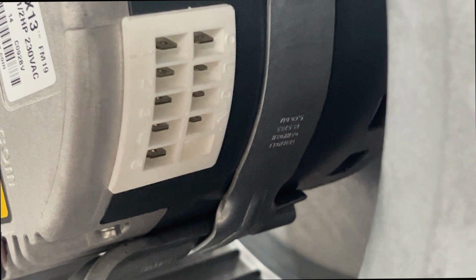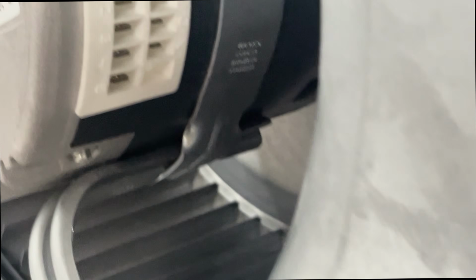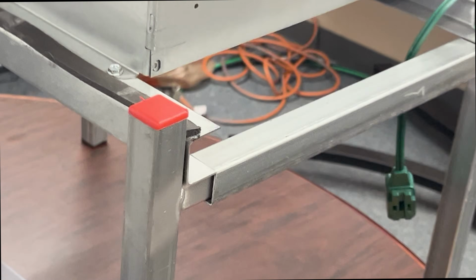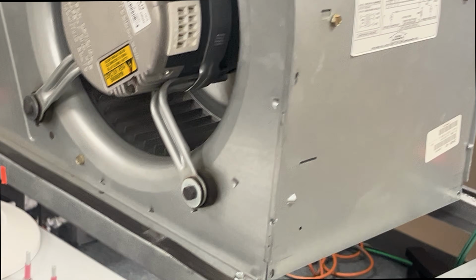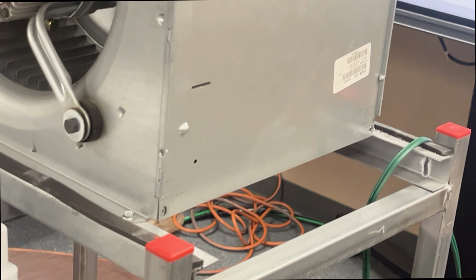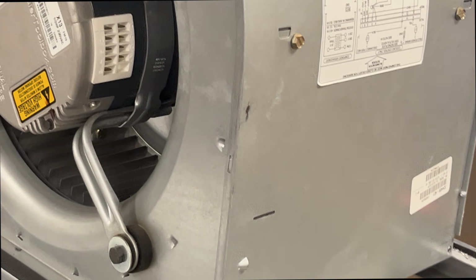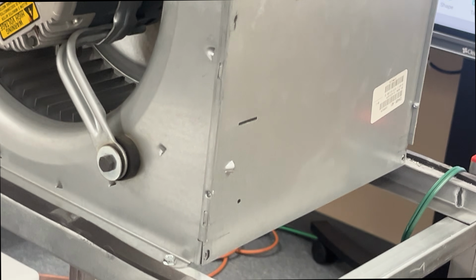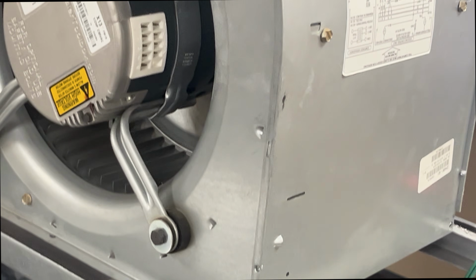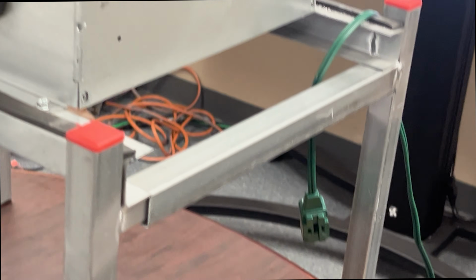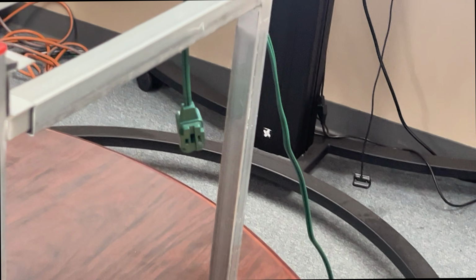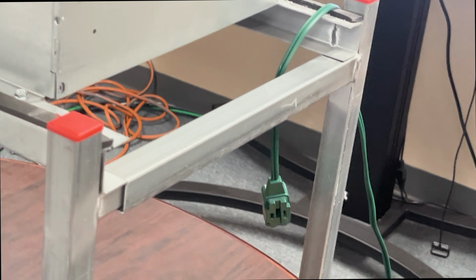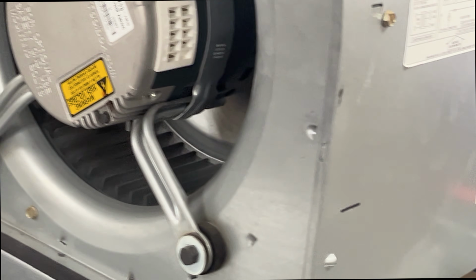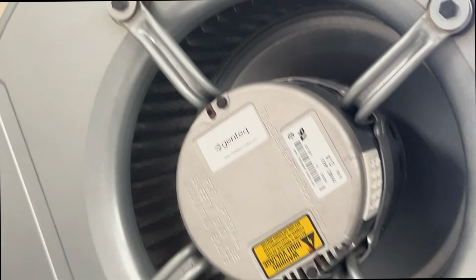I can't give you static in its application because it's just sitting on a free draw air handler stand, as you can see here. It's just sitting here. I got my power supply, I've got the motor, free draw stand, so I'm not able to give you the static pressure to get this motor to pick up in the proper CFMs. Now, if you see here, I got that green extension cord, okay? That's where I'm going to get my neutral from, and I'm going to go ahead and wire that up right now. Just give me a second.